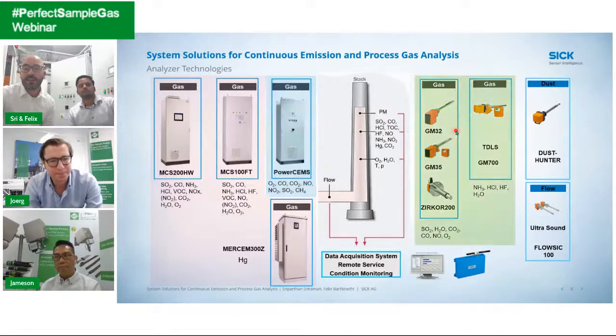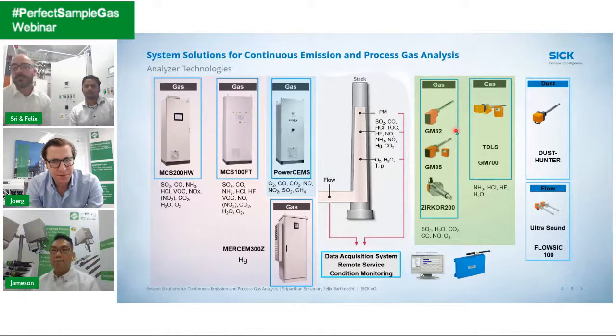The third gas analyzer technology SICK is offering is so-called in situ measurement technology, where the measurement happens directly inside the process without any additional sample handling. The benefit is that you get a very fast reaction to what's going on in the process, and the measurement values are instantaneously available. However, the limitation is mostly related to the limited number of gases which can be measured at the same time.